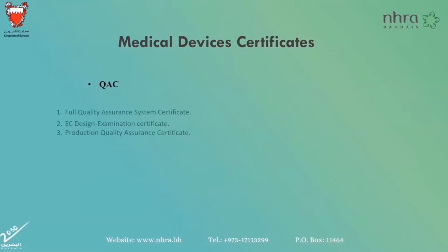For the QAC, we accept only the full quality assurance system, which covers the entire system from design, manufacturing, and final inspection. The EC design is not mandatory, but it's required in some cases, such as if the medical device or IVD risk classification is Class 3 for medical device, or Class D for IVD and registration. But in the importation, it's only required if it was asked for.